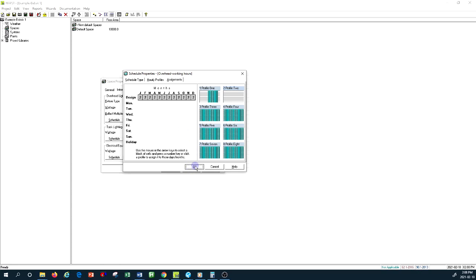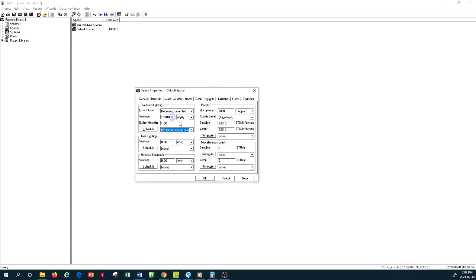Let me go back and press OK. In System Design mode, if I assign the overhead lighting wattage, task lighting, and people — everything complete for that space — Carrier HAP assumes all of these loads are available at maximum. It designs our cooling or air conditioning system based on the full maximum peak internal load.